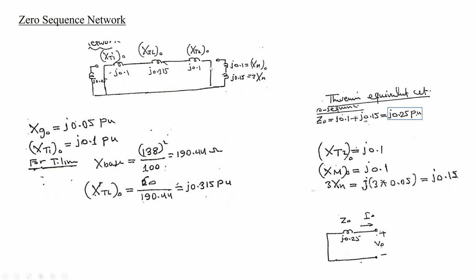So for the fault here, you're going to look from the point of the fault, so you have these two impedances with the 3Xn, and this is the Xn for the motor. So add them together to calculate Z naught, which is the zero sequence. For the zero sequence, you're going to see this here is an open circuit. So for the X base, you have voltage base squared over S base. For the transmission line, this is the X base for the transmission line. Okay, and you have the value for the transmission line, divide the actual by the base, and you will get the per unit.